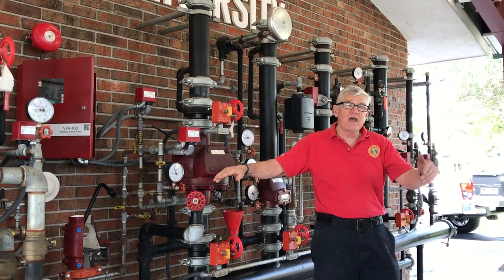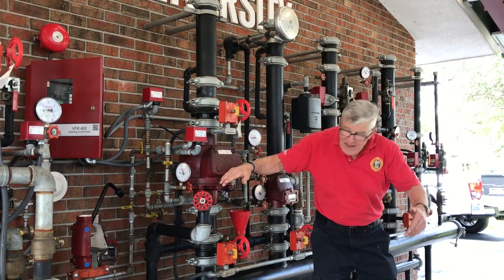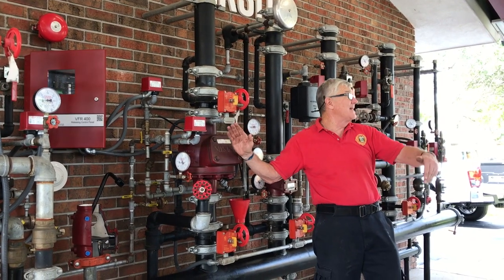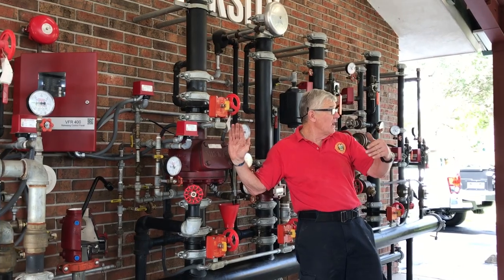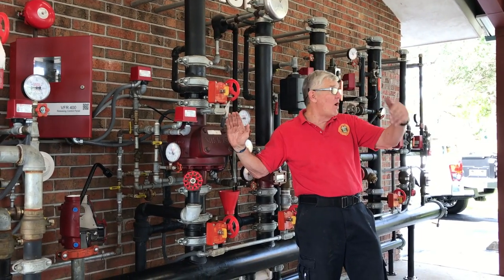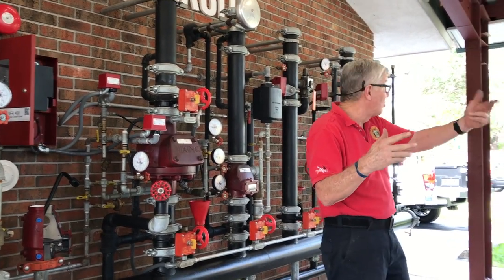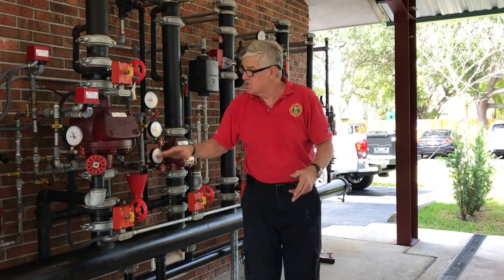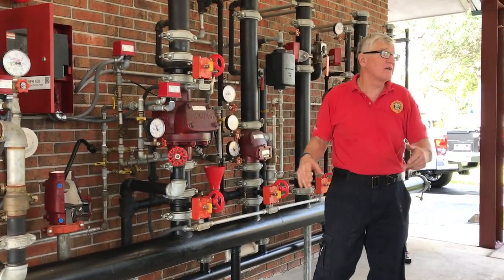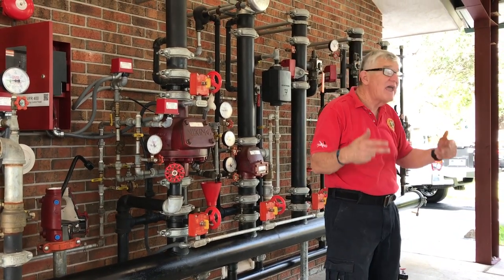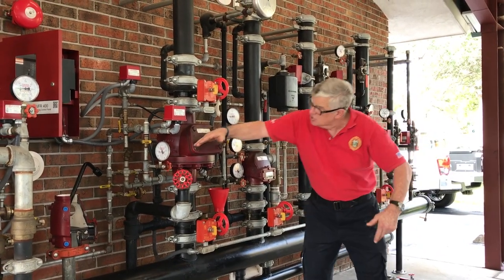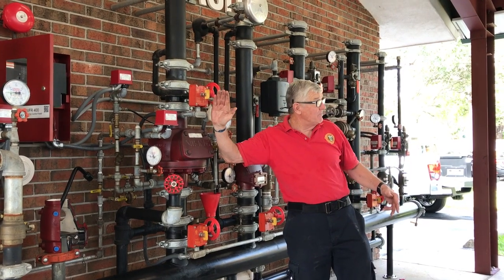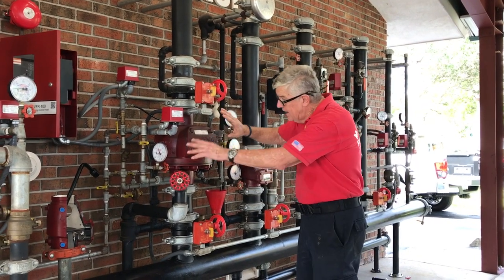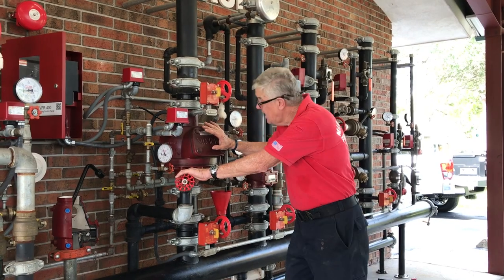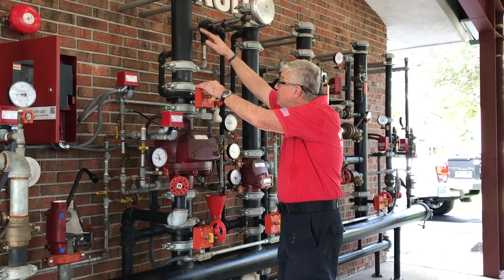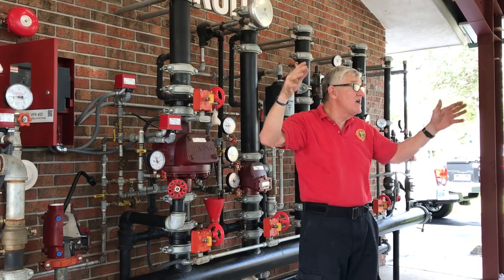When a sprinkler head is activated, it allows the valve to open up and actually latch, which I will show you, and allow water to flow out of the open sprinkler head. First, air will come out. And sometimes these systems will have devices called either accelerators or exhausters to hasten that release of the air so that the valve can pop open. Now, understand that you're going to have an air compressor. And all of this up to here would have to be in a heated area.